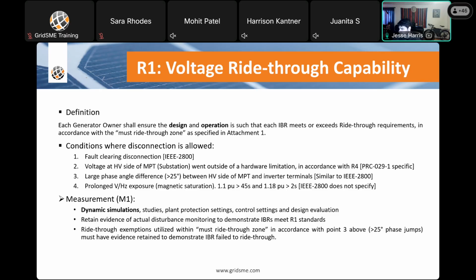Conditions where disconnection is allowed: fault clearing and disconnection. So clearing faults has a priority, and some faults cannot be cleared unless the IBRs disconnect. The second exception, the voltage at the high voltage side of the MPT went outside hardware limitation. So existing IBRs that were built before this standard is implemented could be pushing the voltage and frequency outside of the limits, and it could actually damage the inverters. NERC doesn't expect equipment suicide, so essentially what they're saying here is, go ahead and shut these off if you absolutely have to, or you cannot abide by this standard if you absolutely have to, but it's going to need to be documented and in accordance with requirement R4.